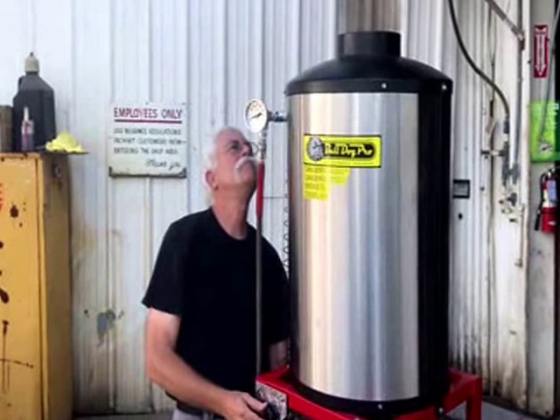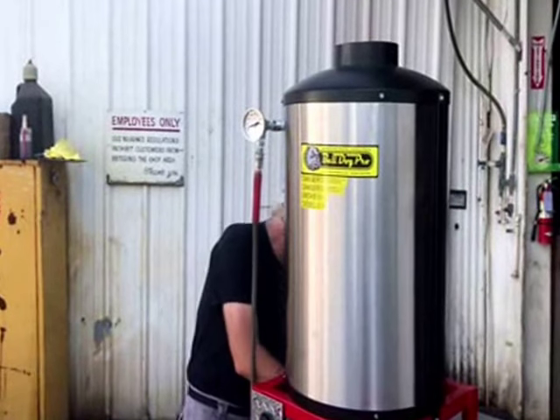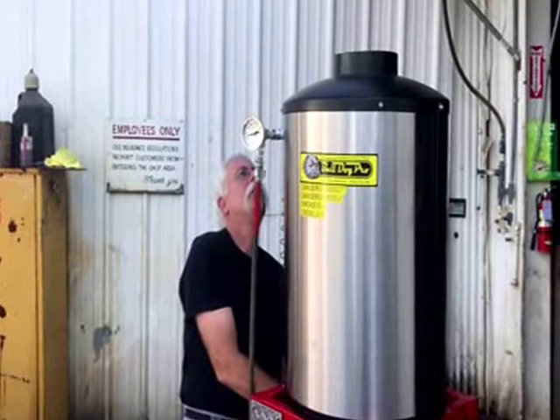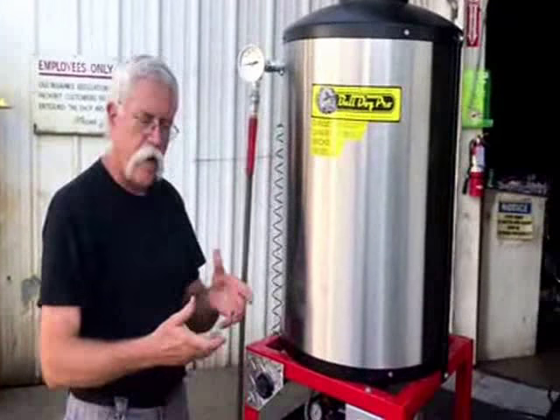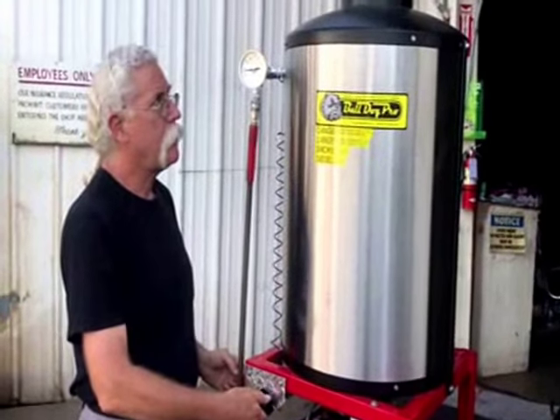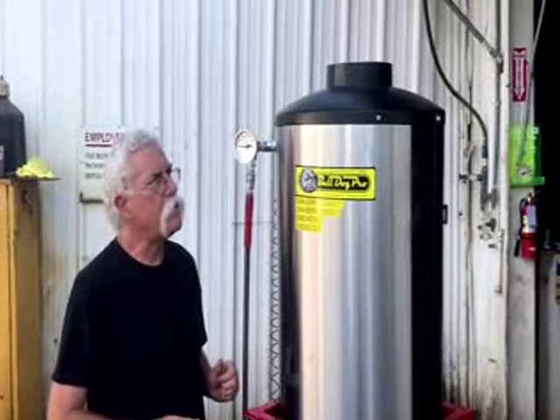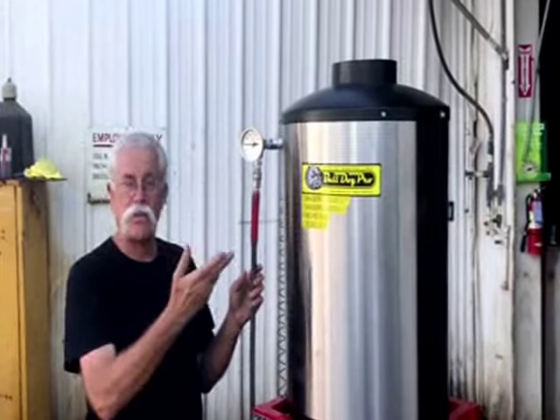I got that black smoke — and now it just cleared. I don't want to give it any more air and I don't want to give it any less. I just want it to be just clear. When it goes off, I get no white smoke. When I turn it on, there's a very tiny little puff before it ignites — not a big deal. If it were giving you white smoke before it ignites, that would mean it wasn't igniting properly.